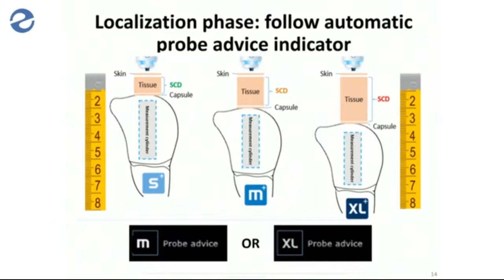You have to look at the skin to liver capsule distance, which is actually automatically measured by the FibroScan system during the exam. So it's pretty important to follow the probe recommendation, which is actually displayed on the screen. It might tell you if you need to use the M probe or XL probe, depending on this skin to capsule distance measured by the system.